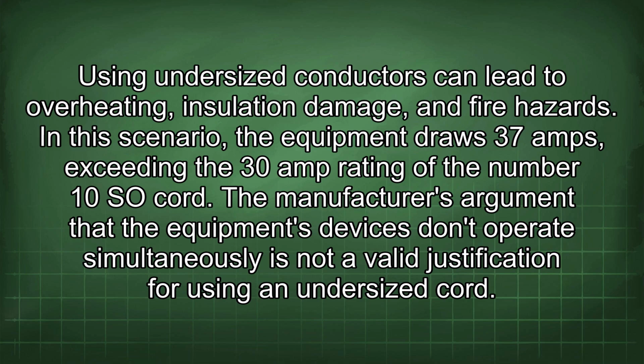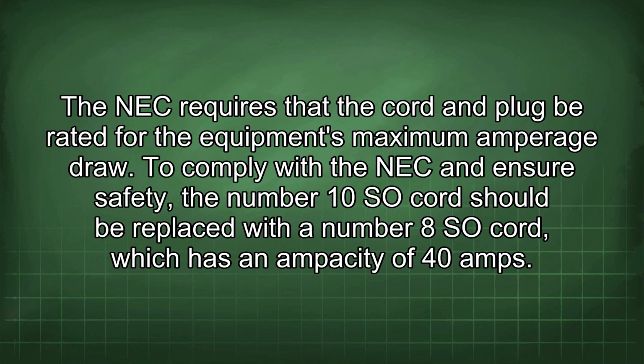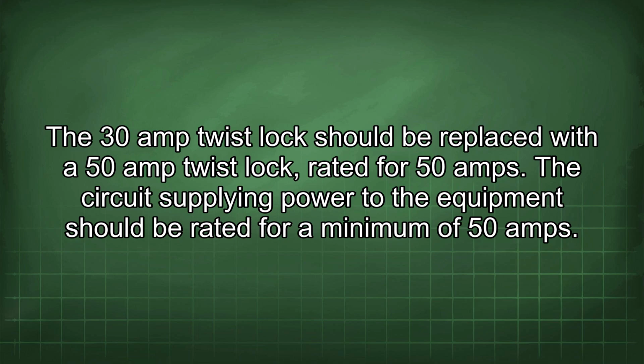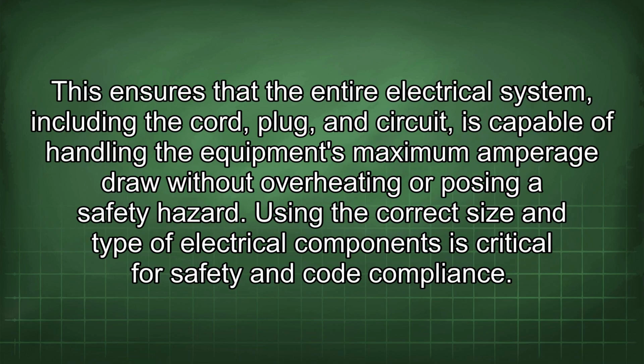In this scenario, the equipment draws 37 amps, exceeding the 30 amp rating of the number 10 SOW cord. The manufacturer's argument that the equipment's devices don't operate simultaneously is not a valid justification for using an undersized cord. The NEC requires that the cord and plug be rated for the equipment's maximum amperage draw. To comply with the NEC and ensure safety, the number 10 SOW cord should be replaced with the number 8 SOW cord, which has an ampacity of 40 amps. The 30 amp twist lock should be replaced with a 50 amp twist lock, rated for 50 amps. The circuit supplying power to the equipment should be rated for a minimum of 50 amps. This ensures that the entire electrical system, including the cord, plug, and circuit, is capable of handling the equipment's maximum amperage draw without overheating or posing a safety hazard.